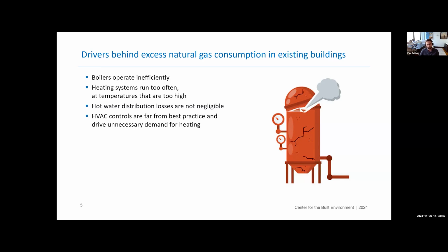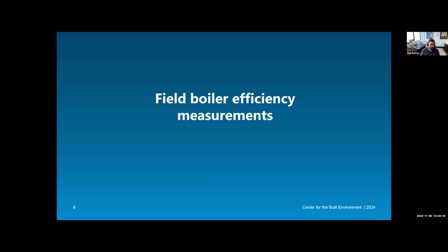And all of these measures, all of these issues combine together and cascade together, right? So if you are running your heating system too often, and you have a little bit of load in there to maintain those distribution losses, and your boiler plant is operating inefficiently, those combine together to waste a really large amount of gas. So we wanted to see how much we can save by correcting all of those issues as much as possible in some existing buildings. So I'll show you some of the results from this project.